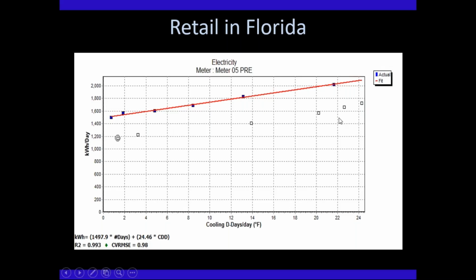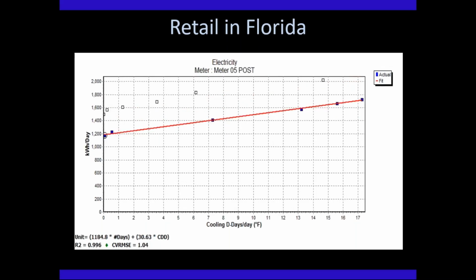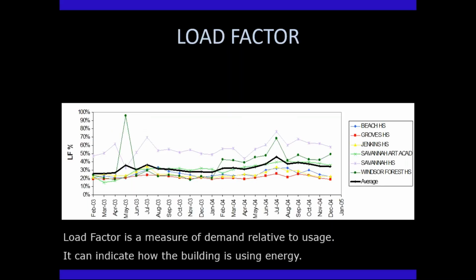What I'm trying to point out with this retail example in Florida is that you can identify changes in usage patterns and identify the type of change—did the slope change, or did the base load change, or did both change? When they do, you're left with a set of guesses. It could be this or that, but at least you know something, and you can go back to the building and ask what happened, then decide if it was a good idea. Okay, that's it for the section on balance points and weather.